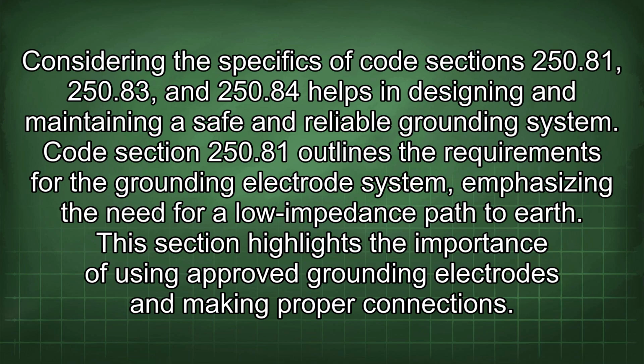Considering the specifics of code sections 250.81, 250.83, and 250.84 helps in designing and maintaining a safe and reliable grounding system. Code section 250.81 outlines the requirements for the grounding electrode system, emphasizing the need for a low impedance path to earth. This section highlights the importance of using approved grounding electrodes and making proper connections.